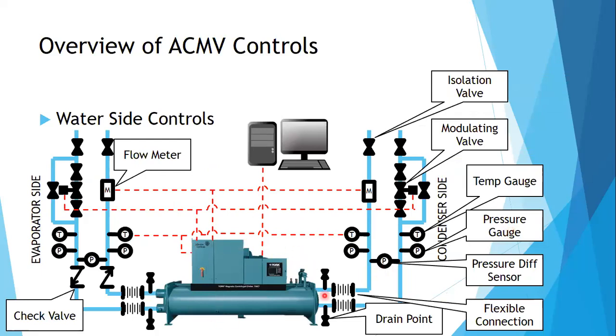Again, this is your chiller. Your chiller has your temperature gauge, pressure differential, flexible connector. Same concept, same principle. Drain points for your installation purposes. Flexible connection to isolate the vibration from the chiller to the rigid pipes. Okay, the flow meter. The flow meter is connected to your chiller, and this flow meter is connected to your chiller. This motorized valve is also connected to your chiller, and this temperature sensor is connected to your chiller.